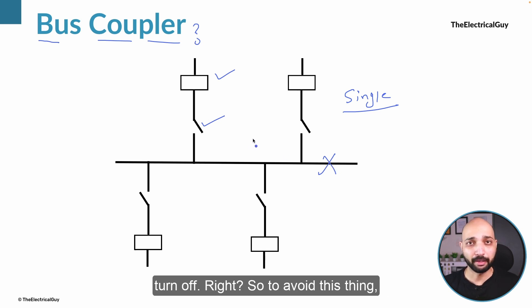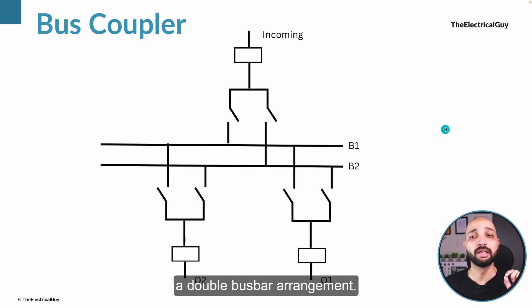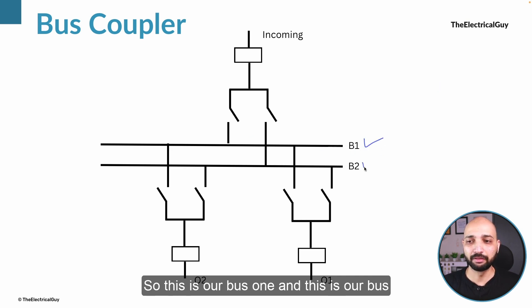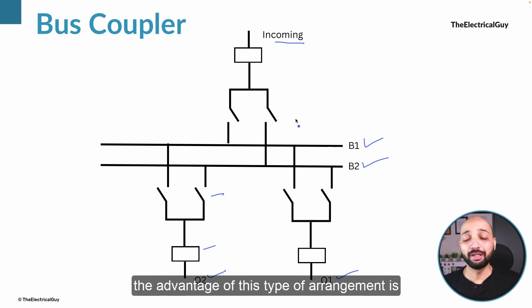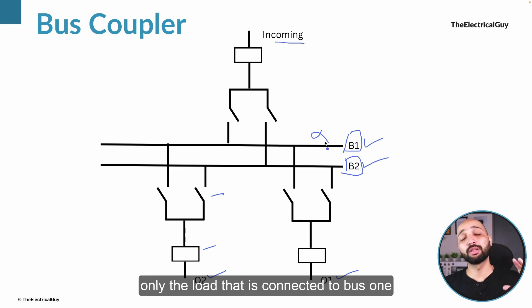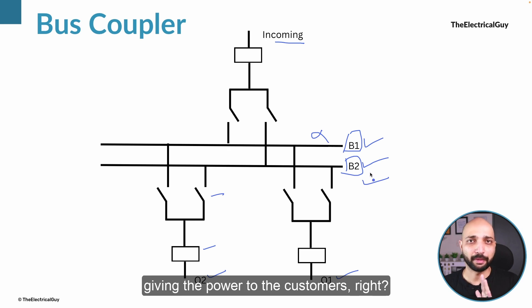To avoid this, we can make a variation and use a double bus bar arrangement. What you can see on your screen is a simple double bus bar arrangement — this is bus one and this is bus two. We have one incoming bay, outgoing bay one, and outgoing bay two. The advantage of this arrangement is that you can connect some load on bus one and some load on bus two, so if there is a fault on bus one, only that load suffers while bus two keeps supplying power to customers.